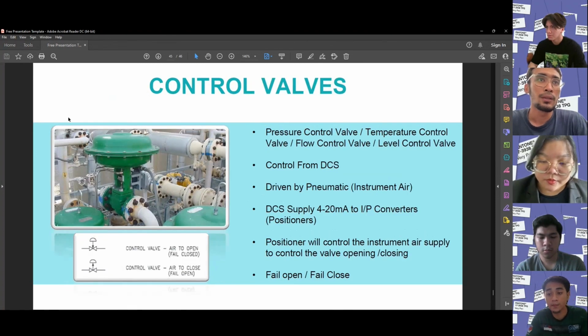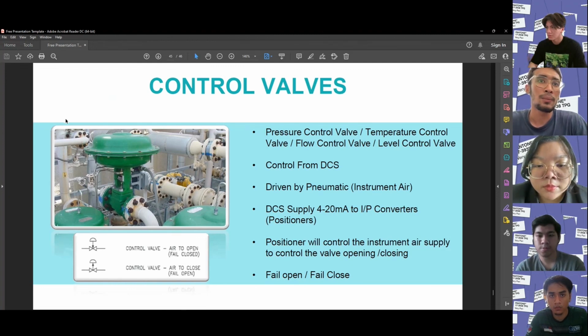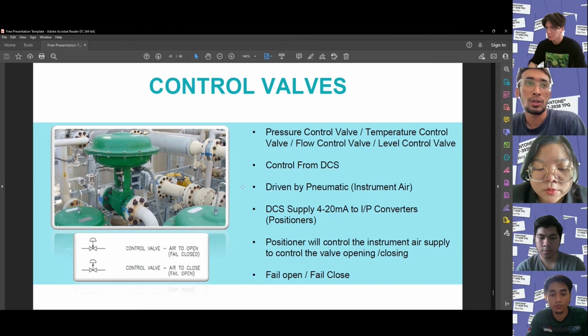Control valve. First, pressure control valve, temperature control valve, flow control valve, and level control valve. Control from DCS, driven by pneumatic instrument air. DCS supplies 4 to 20 mA to the I/P converter. The positioner will control the instrument air supply to control the valve opening and closing. Fail open or fail close.